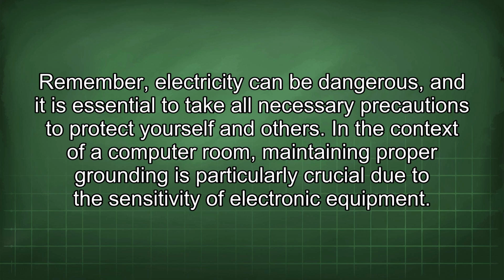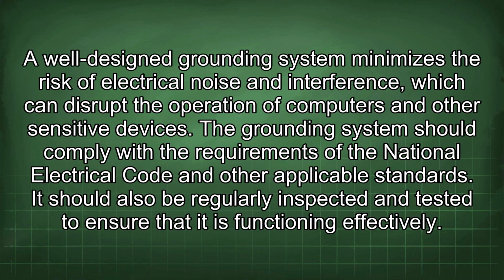In the context of a computer room, maintaining proper grounding is particularly crucial due to the sensitivity of electronic equipment. A well-designed grounding system minimizes the risk of electrical noise and interference, which can disrupt the operation of computers and other sensitive devices. The grounding system should comply with the requirements of the National Electrical Code and other applicable standards. It should also be regularly inspected and tested to ensure that it is functioning effectively.